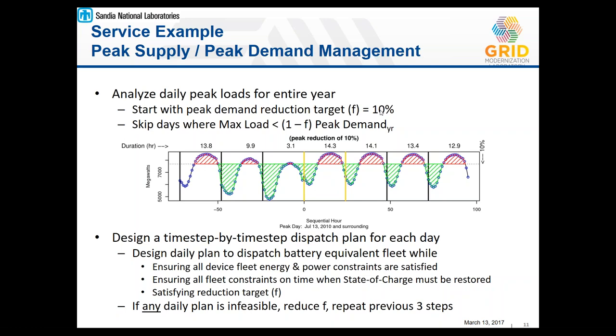So we move from 10% to, let's try to reduce it by 11%. And if it can do that, then we move to 12%, and so on until it can't. And once we know that it can't, we step back and say, okay, one before that, that is the performance of this device fleet. And whether or not that's done behind the meter or in front of the meter, there are many different places where this kind of service can be applied.